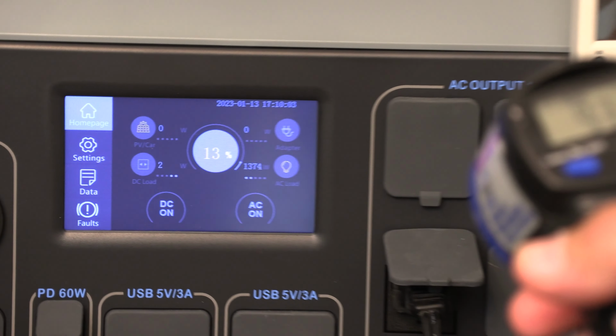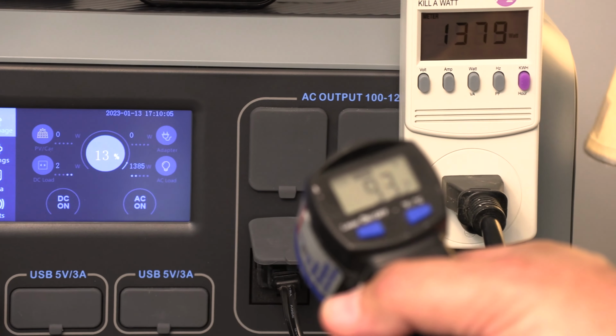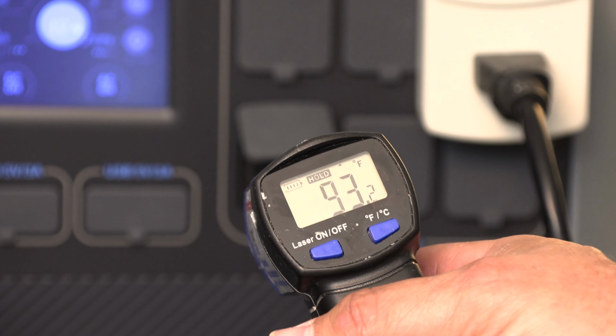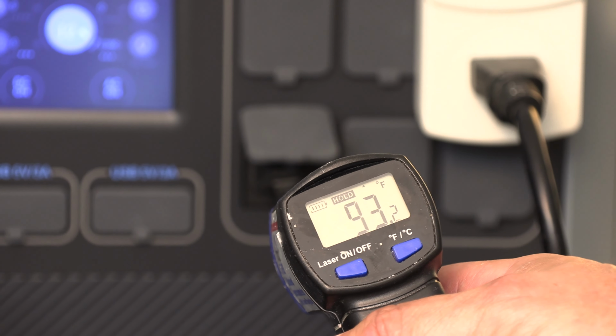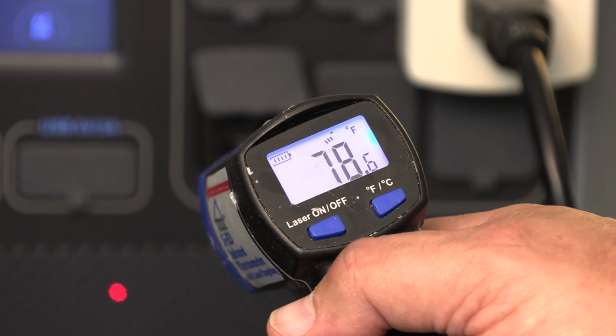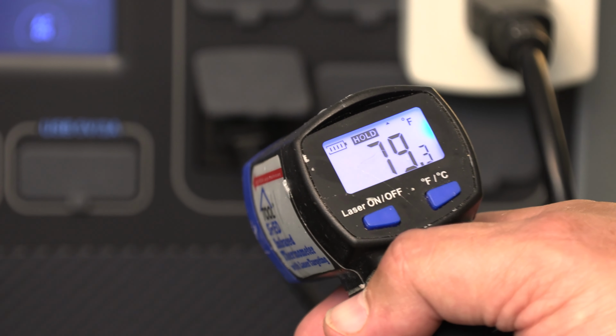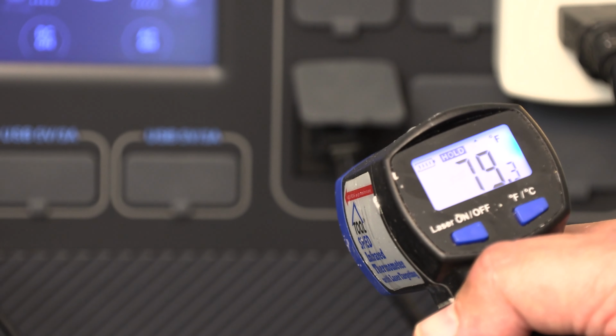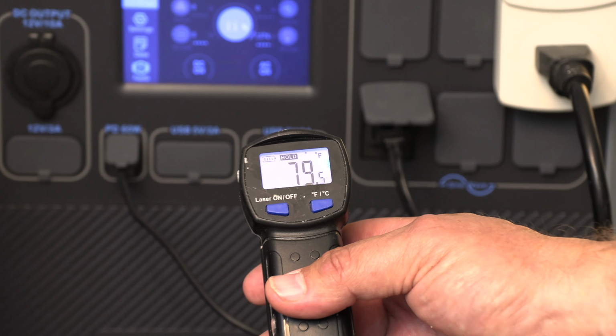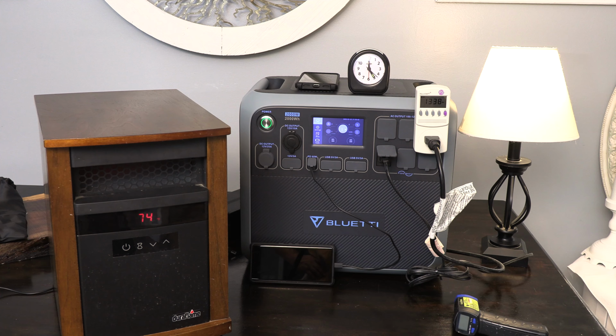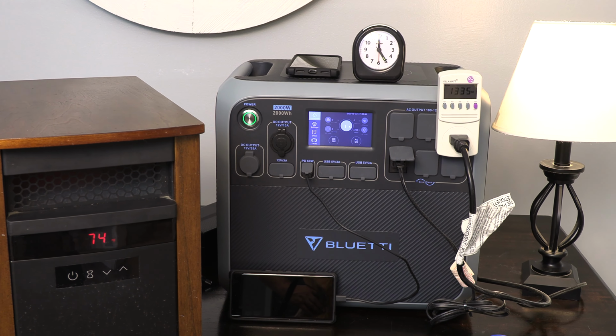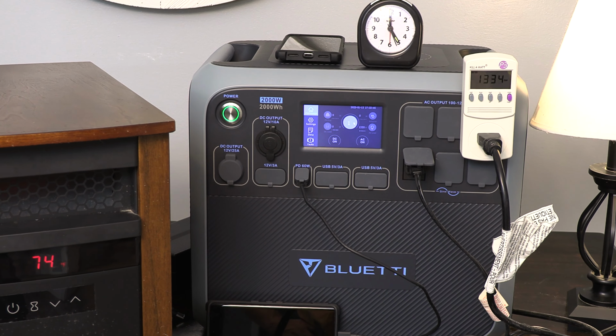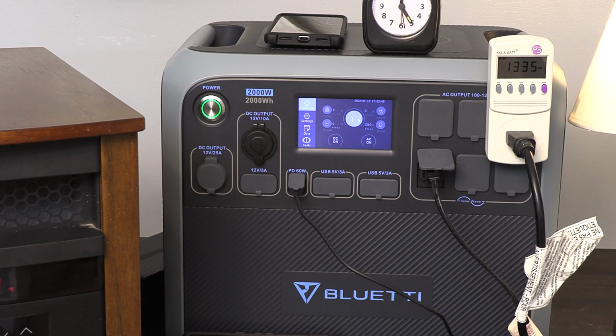Here's an important little note that's often overlooked on these units: it can only work between 32 degrees and 104 degrees. You can still discharge the batteries below zero, however lithium iron phosphate batteries do not like to recharge while below freezing. I'll say this is possibly one of the first cons of this unit, and it's not really a con, it's just something you have to be aware of.